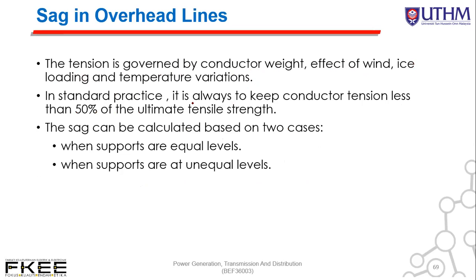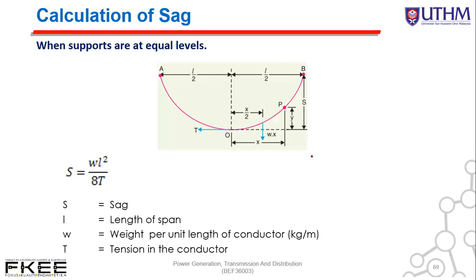Kemudian, in standard practice, it is always allowed to keep conductor tension less than 50% of the ultimate tensile strength. The sag can be calculated based on two cases. Yang pertama, when supports are at equal level. Yang kedua, when supports are not at equal level. So we will see the example after this.